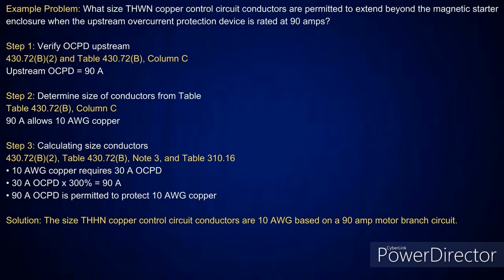Now, this is where you're permitted to extend beyond the magnetic starter. So that means it's not inside an enclosure. In other words, I'm running a conduit over to it. It's some type of raceway, and you'll see it says upstream overcurrent device protected to be 90 amps. Well, if you look in table 430.72(B), column C, so now I'm in column C instead of B, it's going to tell you 90 amps allows a number 10. But look at this. I'm not in free air going over there, so now I have to use table 310.16, and it's going to tell you in note 3 to apply 300%. If I look at a number 10 copper conductor, it's good for 30 amps. I take that at 300%, gives me 90 amps, and it tells you therefore 90 amps could protect number 10 conductors. So it's proven the point there.